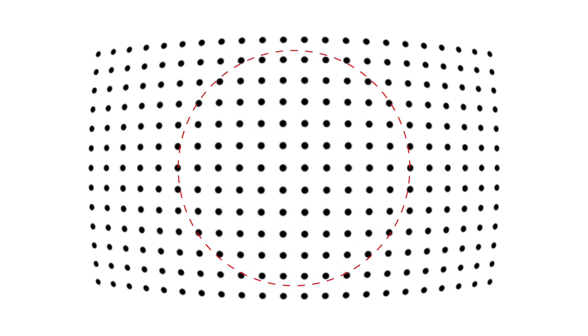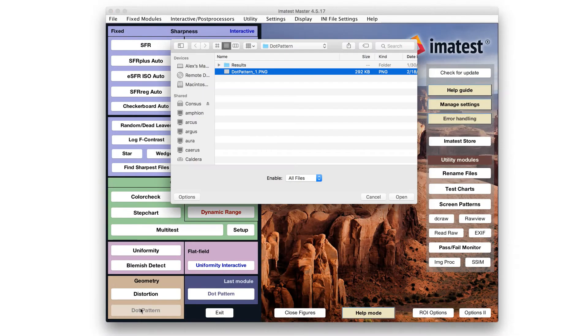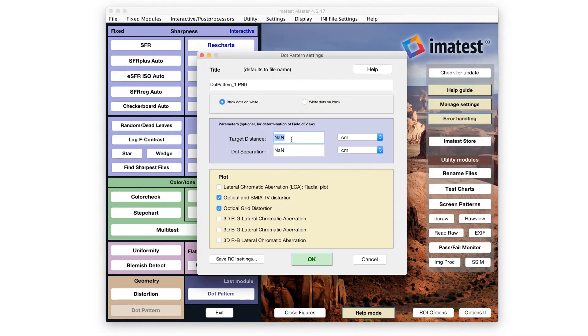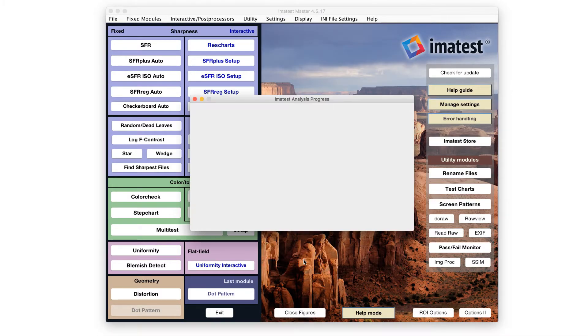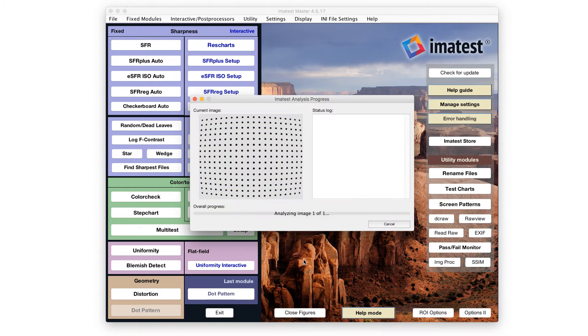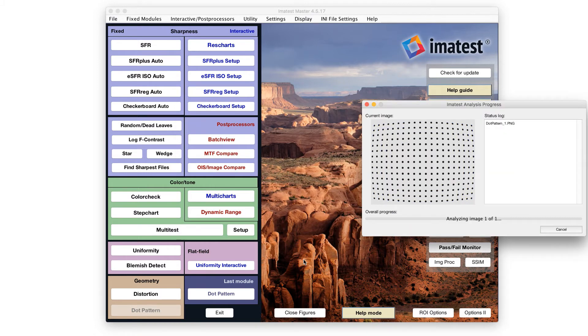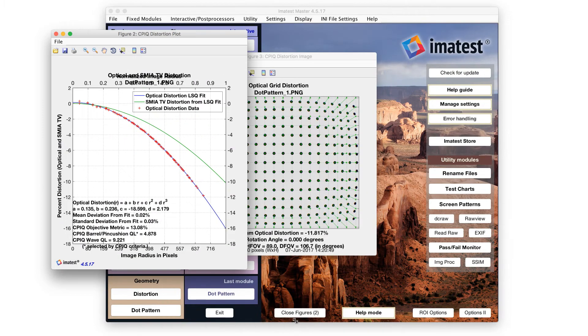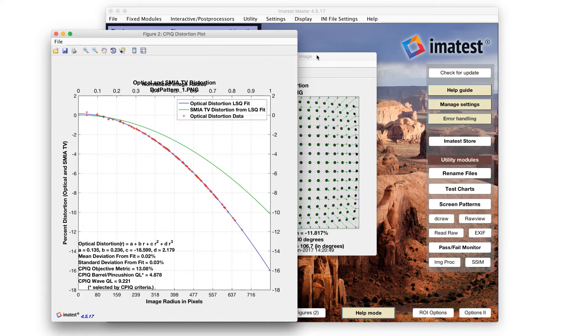Radial geometric distortion is determined by comparing observed radial locations in an image to their ideal locations. The maximum distortion percentage is reported, with positive values indicating pincushion distortion and negative values indicating barrel distortion.